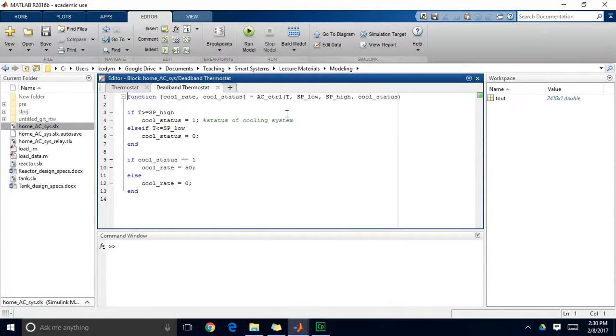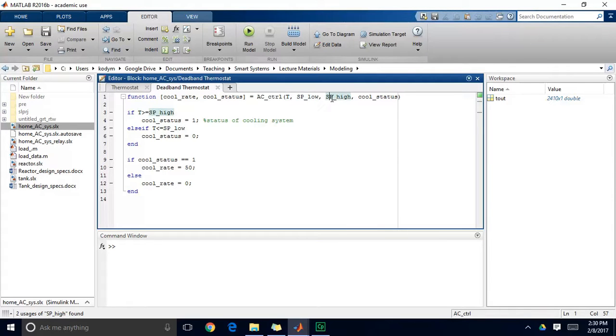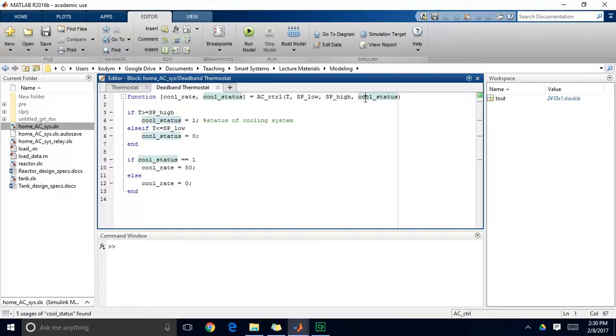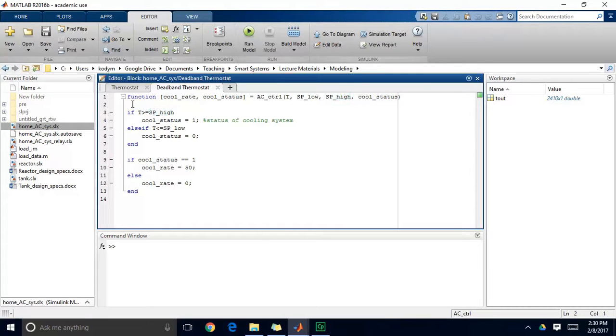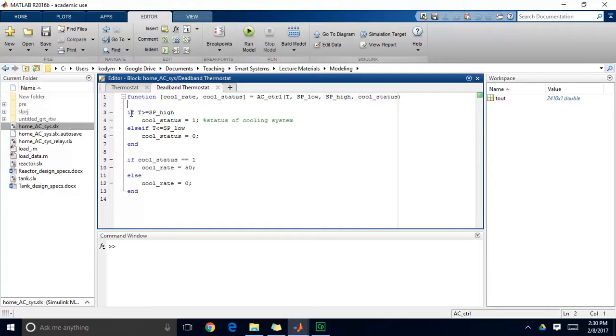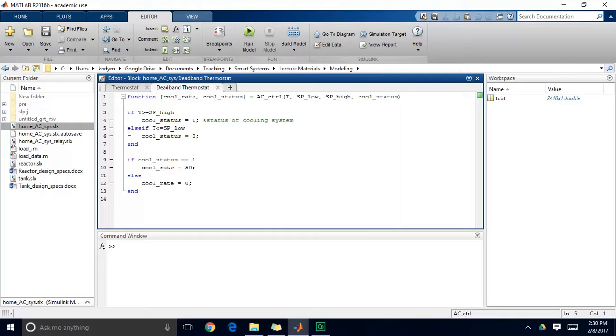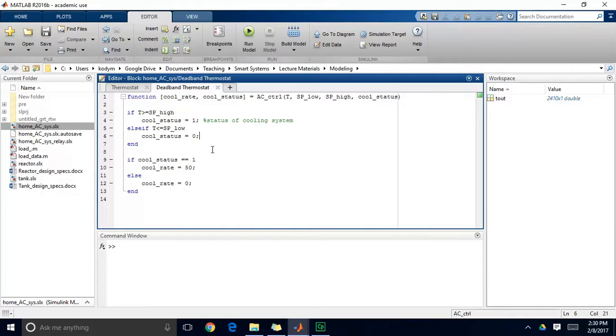So my function inputs are the actual measured temperature, my low set point, and my high set point. And I have another variable called the cooling status. The cool status is a binary variable so it's one when my cooling system is on and it's zero when my cooling system is off. So I'll walk you through the logic here. If my temperature exceeds the high set point then I want to set my cooling status to one. I want to turn on my cooling system. And I don't turn it off until my temperature goes below the lower set point. And in that case when that happens I set my cooling status equal to off.